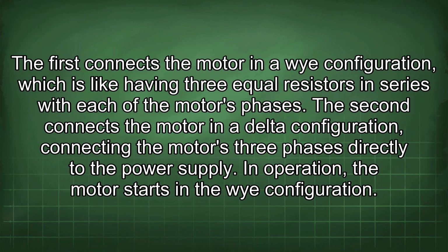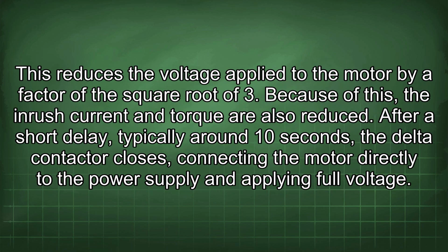The first connects the motor in a Y configuration, which is like having three equal resistors in series with each of the motor's phases. The second connects the motor in a delta configuration, connecting the motor's three phases directly to the power supply. In operation, the motor starts in the Y configuration. This reduces the voltage applied to the motor by a factor of the square root of 3. Because of this, the inrush current and torque are also reduced.